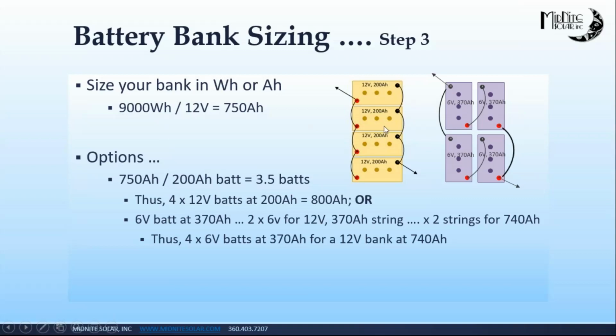I've got 2 examples here, this one and this one. Starting with this one: 750 amp hours divided by a single 200 amp hour battery says I need 3.5 batteries, so I'll round up to 4. We have 4 batteries, each 12 volts at 200 amp hours, giving me 800 amp hours. This is actually a little larger than what we need, but it's as close as we can get.